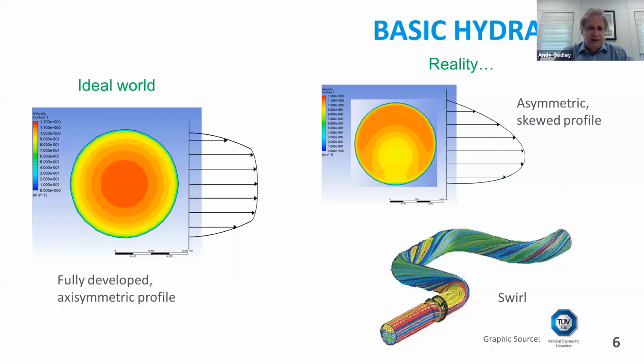And most of those test rigs are quite idealized situations. So they have what tends to be referred to as a fully developed axisymmetric velocity profile, where the water flowing through the pipe is moving in well-defined streamlines, and there is a nice clear structure to the profile. But obviously in real life, that rarely happens. We have bends, we have fittings, we have all kinds of disturbances in the pipes that mean that the flow can be distorted, whether that's distorted asymmetrically, as in that top right-hand picture, or in some cases where we get swirl, so the water is corkscrewing along the pipe, as in that lower picture. And this can really affect the performance of our meters, as we shall see.